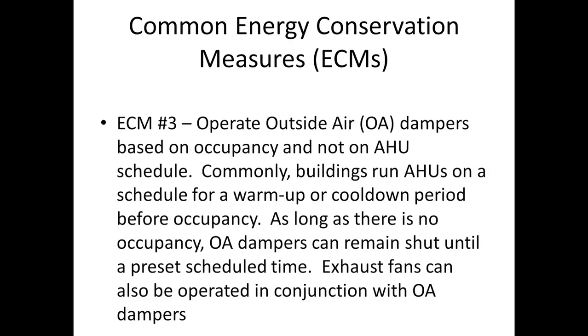Operating outside air dampers based on occupancy and not on AHU schedule. This goes for both supply, outside air, and exhaust air. This is operating based on occupancy. When there's no one in the building, there really doesn't need to be ventilation. If there is ventilation, it needs to be very minimal. We can operate outside air really only when the building's occupied. And this allows us to save energy during those non-occupied hours at night and on the weekends, which a lot of buildings don't think about or don't have incorporated into their control logic.